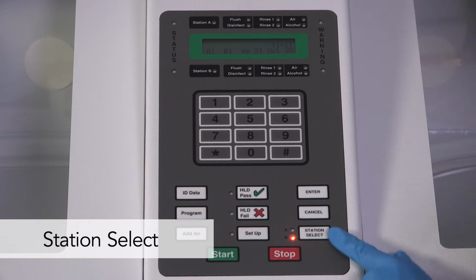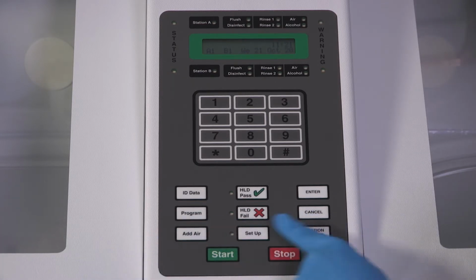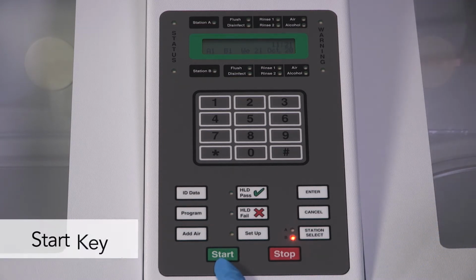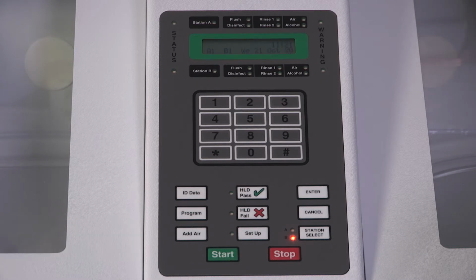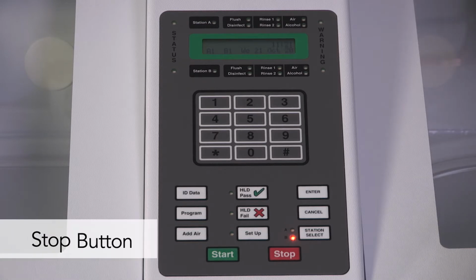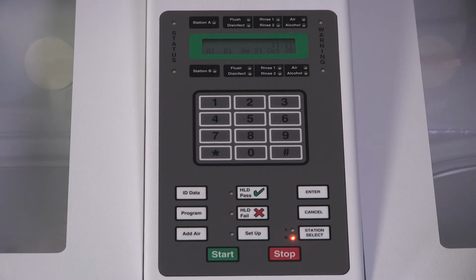Pressing Station Select will toggle to either Station A or B. The highlighted station is the selected station. Press the Start key to begin the disinfection cycle, or to resume an interrupted cycle in the selected station. Press the Stop button to pause a disinfection cycle in the selected station. You can also use Stop to acknowledge a warning message, or stop a system function. You must use the Stop button to reset the DSD EDGE Reprocessor when a leak fail message is displayed. The leak test system is discussed in the Operations segment.